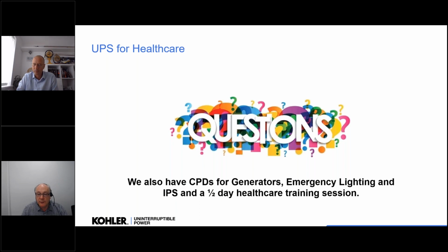Instead of installing multiple isolation transformers, we're looking at installing a paralleling neutral contactor at section board level. The section board is dual TX supplied. The theory is that the paralleling neutral contactor will be designed in such a way that a neutral connection will be maintained and made before any planned or unplanned switching at section board level. I'd be interested to know your thoughts on this arrangement.